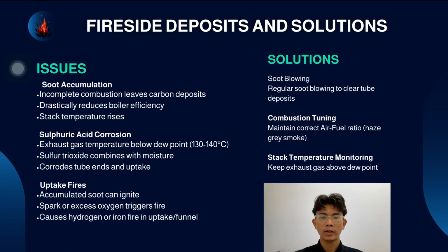Finally, we have fireside deposit. Incomplete combustion leaves carbon deposits, which reduce heat transfer efficiency. There are two main risks here. First is sulfuric acid corrosion. If exhaust temperature drops below the dew point, 130 to 140 Celsius, sulfur compounds combine with moisture to corrode the uptake.